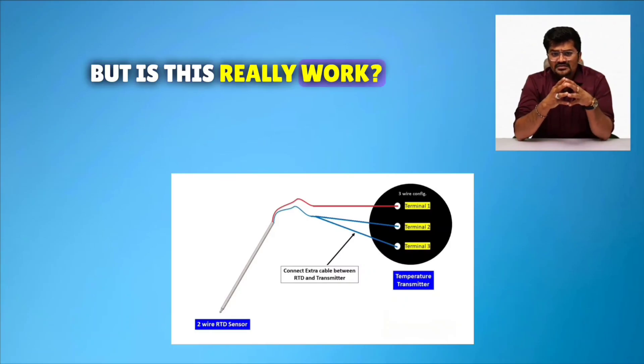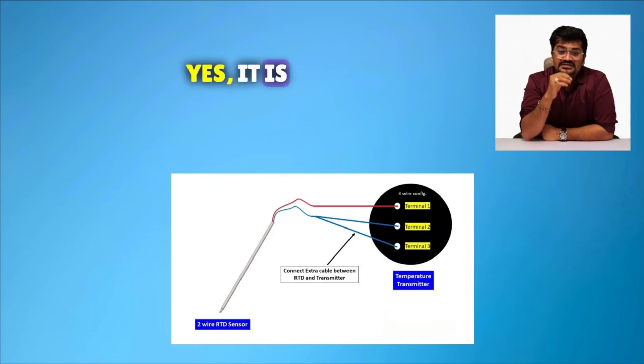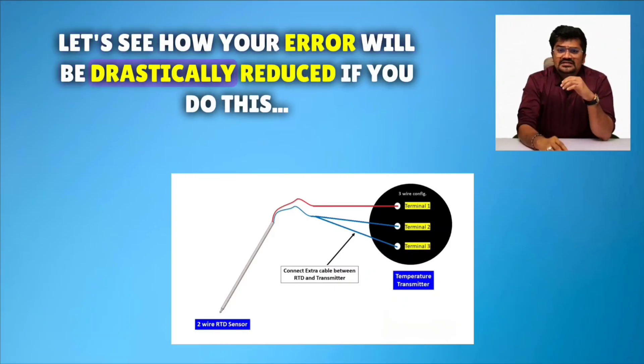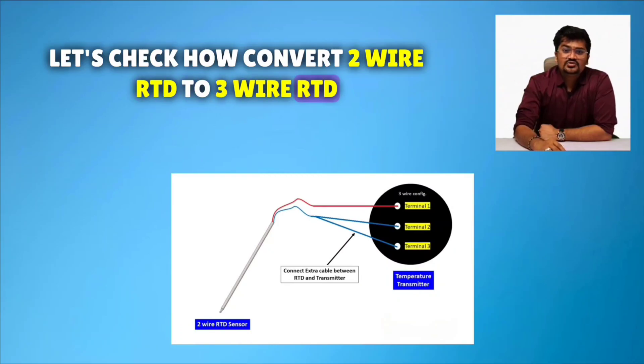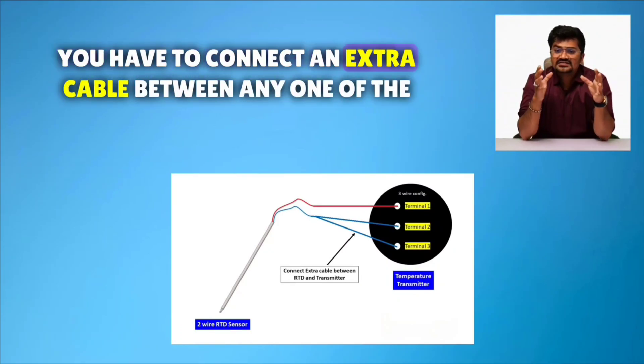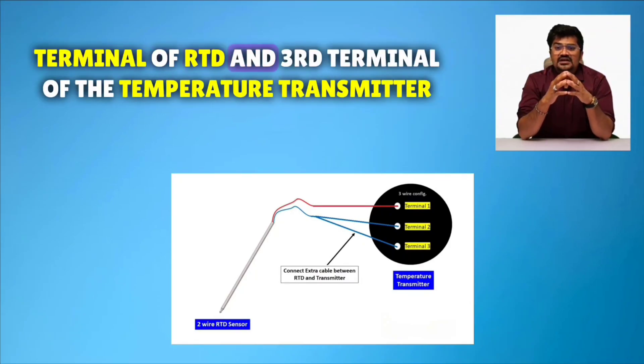But is this really work? Yes, it is. Your error will be drastically reduced if you do this. To convert 2-wire RTD to 3-wire RTD, you have to connect an extra cable between any one of the terminal of RTD and 3rd terminal of the temperature transmitter.